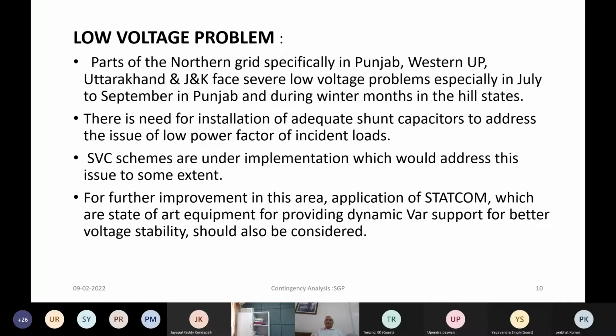Apart from high voltage, we also face the low voltage problem. Again, these are statements taken from the contingency planning report of CEA, where it is said that parts of the northern grid, specifically Punjab, Western UP, Uttarakhand, and J&K, faced severe low voltage problems, especially in July to September in Punjab, and during winter months in the hilly areas. There is a need for installation of adequate shunt capacitors to address the issue of low power factor of these loads.